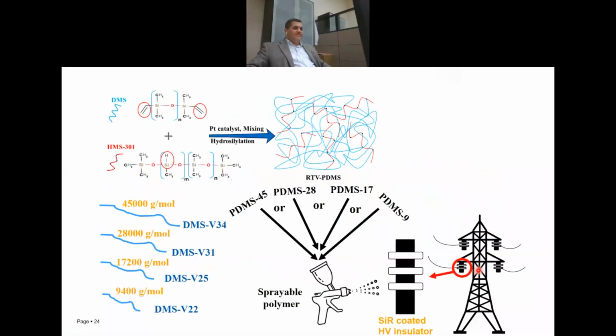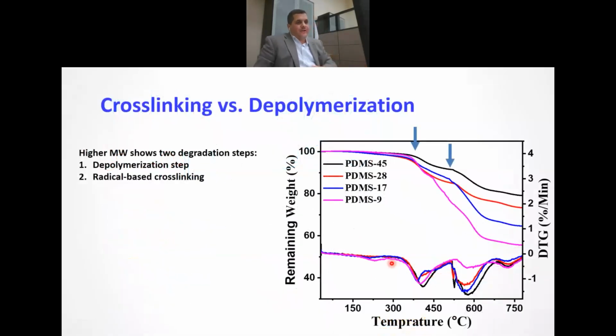So yeah, it is done through spraying, and we use the ceramic tiles, which is typically accepted. And for those coatings, we started to look at the material science part, the material characterization part. This is typical TGA. TGA is very important in this kind of application because the thermal stability is very important. When arcing happens, an electrical arc mainly creates heat, and the dissipation of heat is very important. So the thermal conductivity, or the thermal stability of the material, is very, very important.